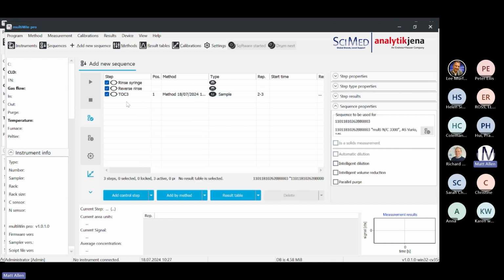So we'll just add one more line to this. We'll add this TC method here as well. So you can see now we've got a TOC method in vial 1, then just a TC method in vial 2. And you can see the methods here. We've got the type here. So this is running it as a sample. It could be a calibration. It could run it as a QC check. So this can all be set up here.